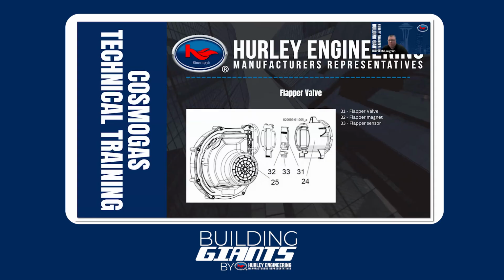Now, because we're putting 4 heat exchangers in one cabinet, or up to 4 heat exchangers, these boilers are essentially common vented. So if we have 2 heat exchangers and we didn't have what they're calling this flapper valve here in the depiction, then we would potentially flow flue gas back down through our other burners and then out the intake and into our cabinets.